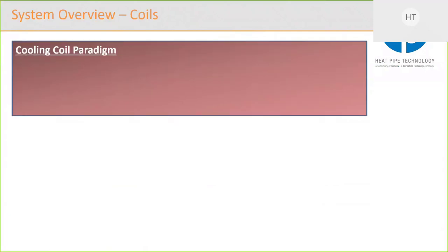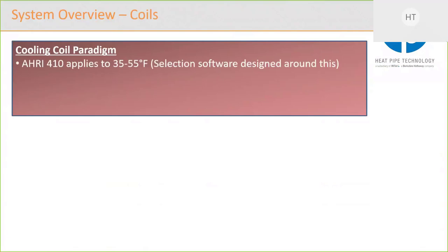So a quick look at the coils. First of all, I want to look at what would happen with a cooling coil, and then challenge that and say, well, this is what we're doing with energy recovery. So when you're designing a cooling coil, often you'll buy a coil that is certified AHRI 410. That applies for chilled water between 35 and 55 degrees. So that's a relatively narrow band.